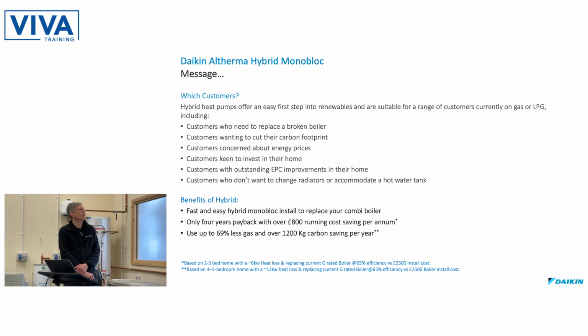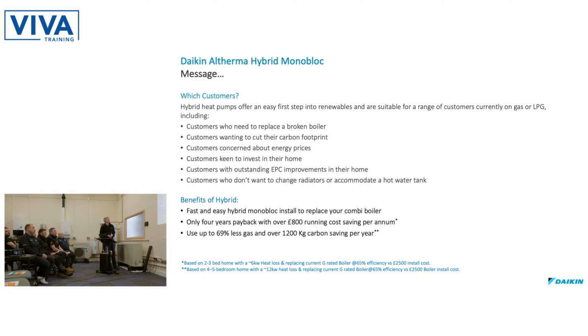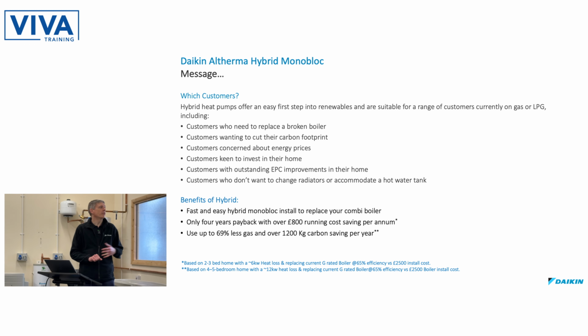So as I mentioned before, which customers are we looking at for this? Those replacing a broken boiler, or customers who want to cut their carbon footprint and reduce their gas usage. They want to invest in their home and start adding renewables, but perhaps they can't go down the full route of changing the radiators and putting a hot water tank in, because obviously that significantly adds to the cost of putting a heat pump system in. So it's a fast and easy installation, hybrid. We're expecting it to be installed in less than 2 days for most systems. You might even be able to get it into 1 day if you've got a couple of people on it, and you can get the electrician in there as well.